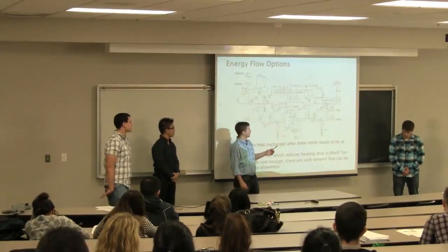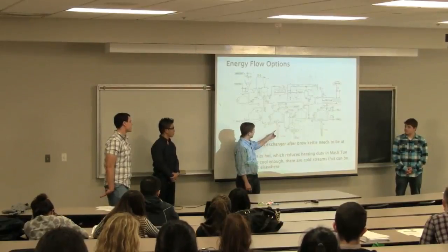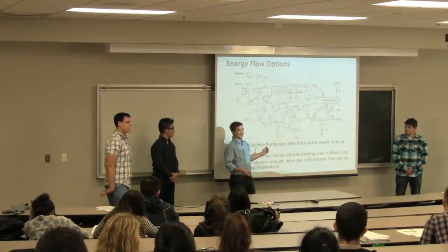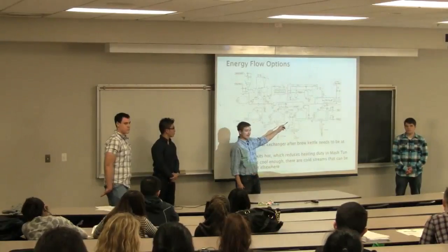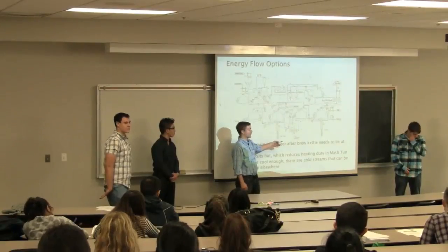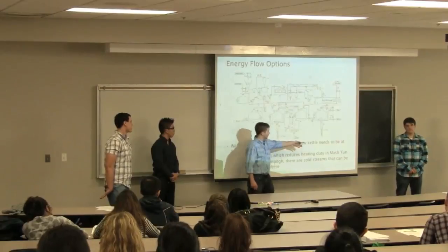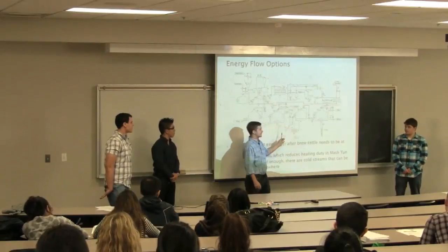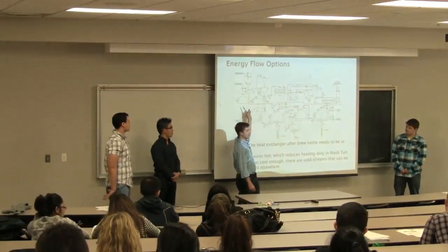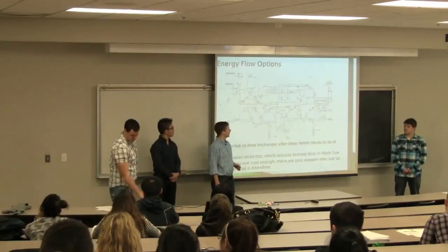So, say in the summer when it comes in a little hotter, they can use these cool streams from these tanks on their way back to the chiller to bring it back down to 6.5 degrees. This one comes into the aging tank at less than negative 0.5, and this one comes in at less than 9 degrees. So you can see that if the feed water comes in too hot, they can cool it easily, and then it gets heated, and they can use that in the cooling process.